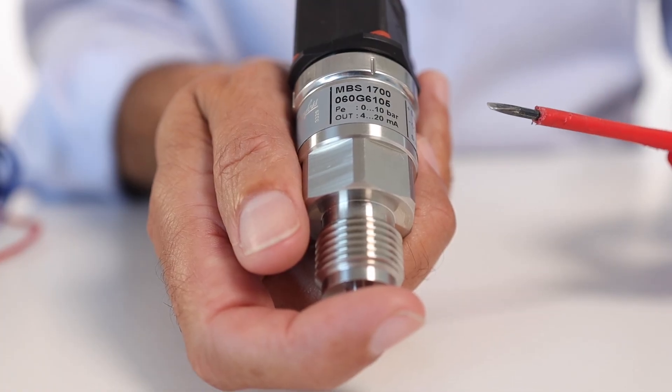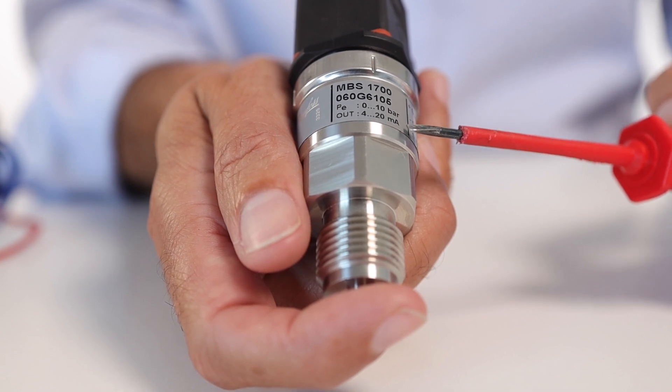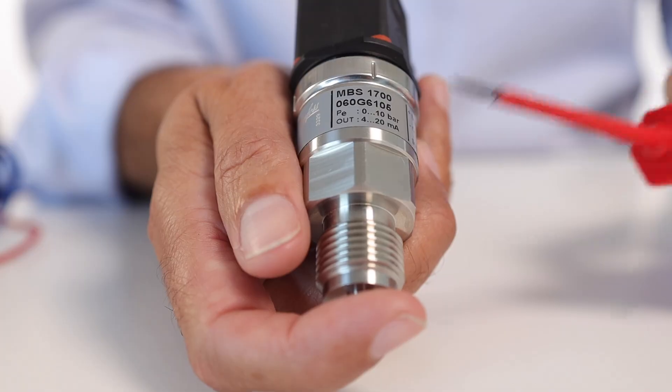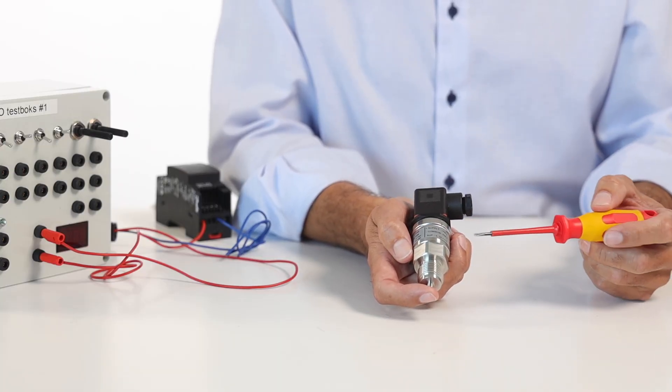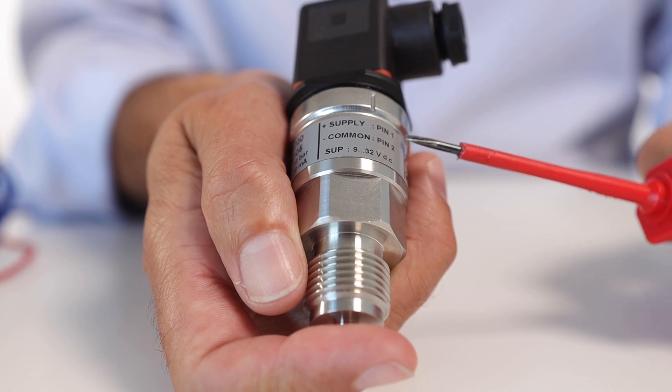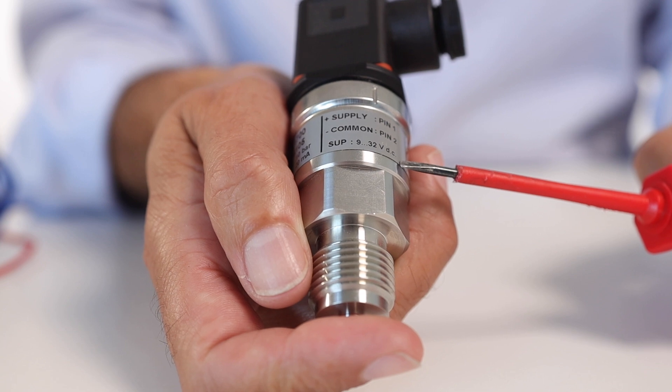On the label on the pressure transmitter, you can see that the pressure range goes from 0 to 10 bar and the output signal is 4 to 20 milliamps. You can also see that plus should be connected to pin 1 and minus to pin 2, and that the supply voltage goes from 9 to 32 volt DC.